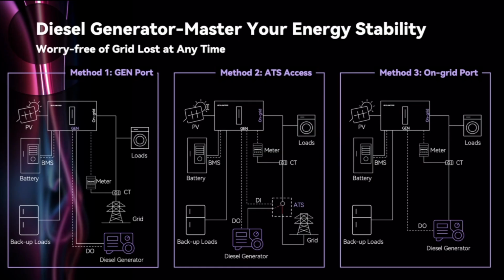And the third method is connecting the generator through the on-grid port, where the generator simply acts as the simulated grid to power the system. In addition, we also offer smart control options for the diesel generator solution. You can choose to start the DG manually via our app, or automatically based on the grid status, or even automatically based on the battery state of charge. So with these options, the system can stay flexible and fully prepared, so your energy will never stop no matter what happens to the grid.